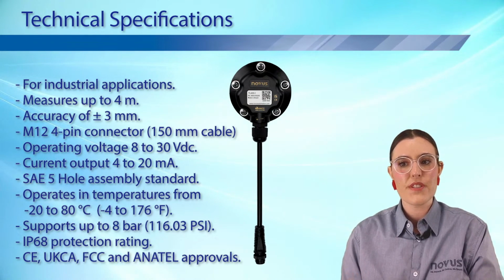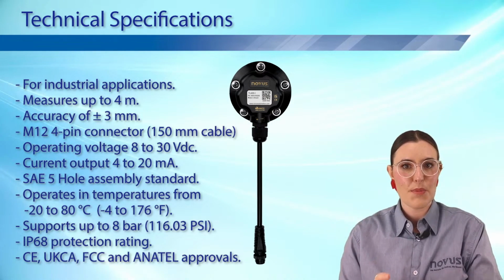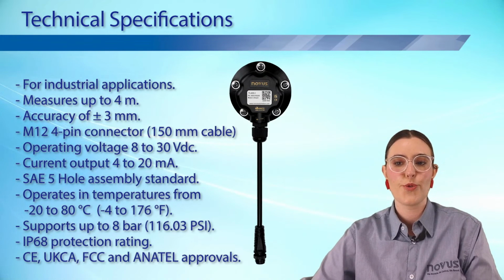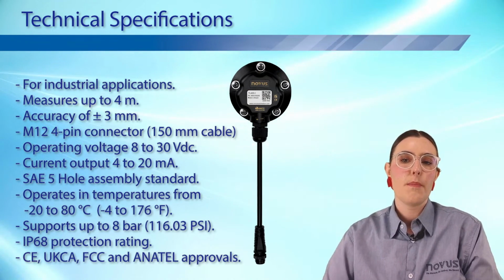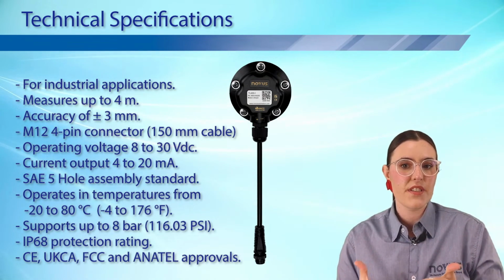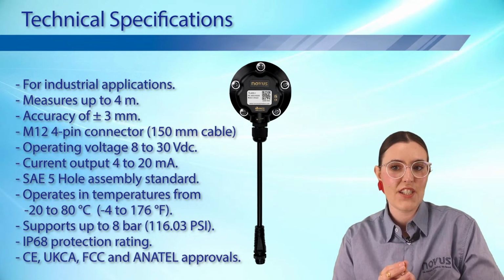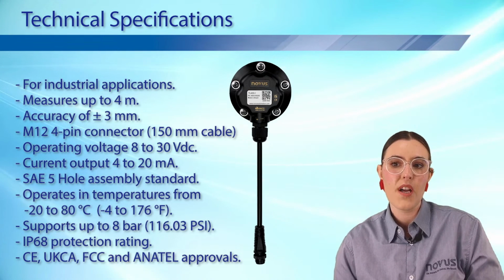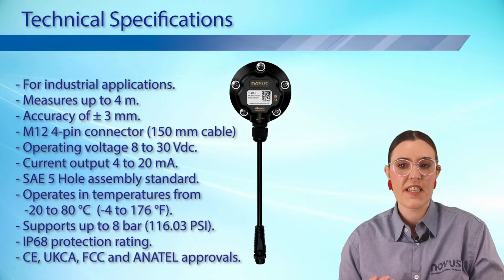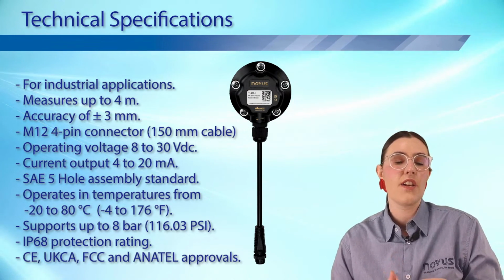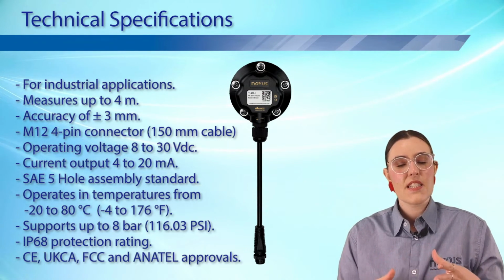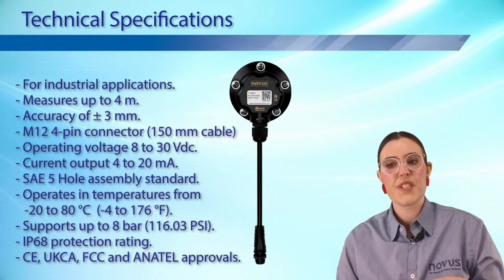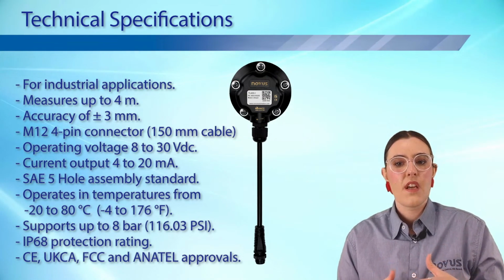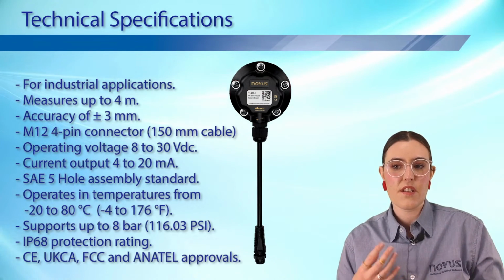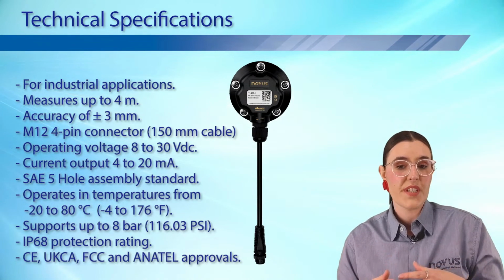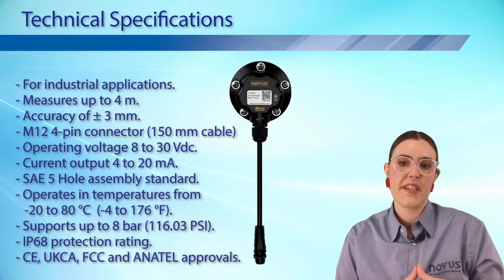TL400-I was designed for industrial use, therefore it is robust and resistant for this type of application. It measures distance of up to 4 meters with an accuracy of plus or minus 3 millimeters, which is excellent accuracy. In order to facilitate installation, it has a 150 millimeter cable and an M12 4-pin male A-coded signal connector, a standard widely used in I/O remotes and other industrial devices. Since it was designed for industrial use, its output retransmits the reliable 4 to 20 milliamp standard. The mounting standard allows it to be installed in both automotive and industrial tanks, and it was developed for outdoor applications in harsh environments.